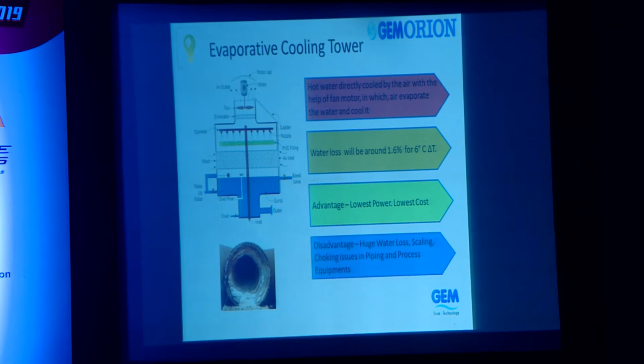So this is a conventional cooling tower, just an indication. I will not elaborate much on that. Theoretical evaporation can be from 0.7 up to 1.5%, including blowdown. And if proper blowdown or water quality is not maintained, this is what you see: a lot of salt formation. If you directly send this water into the mold, obviously the mold's channels and passages can get choked, resulting in hot spots or areas where the cooling process cannot happen, and product quality rejections and productivity are also affected.